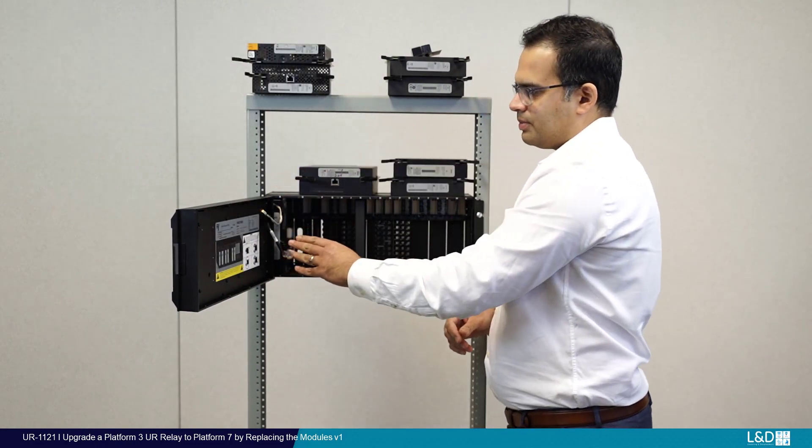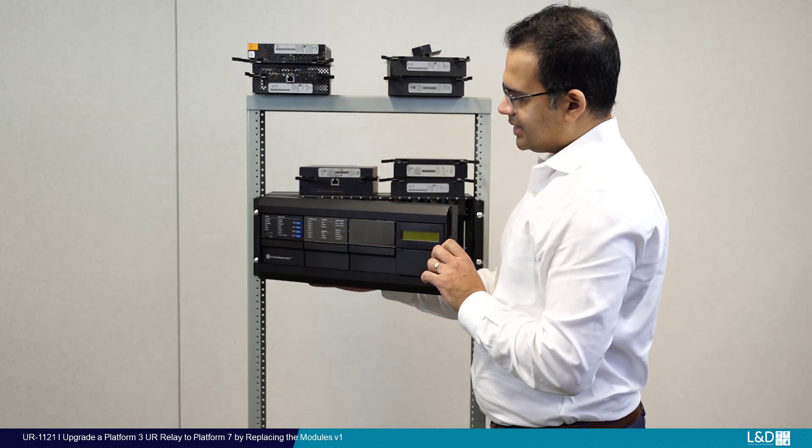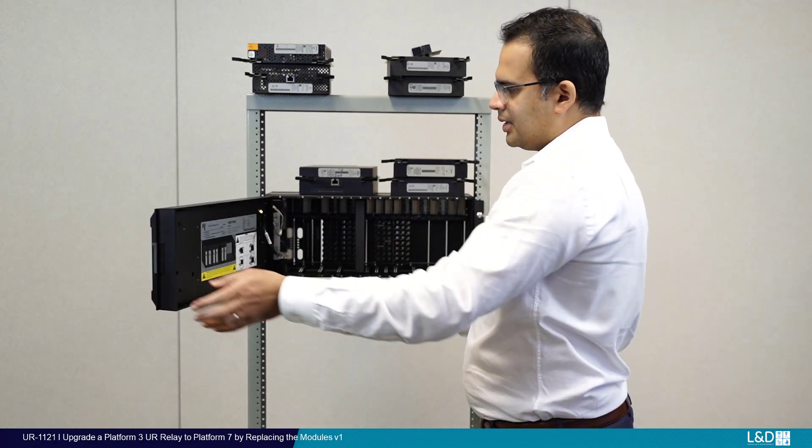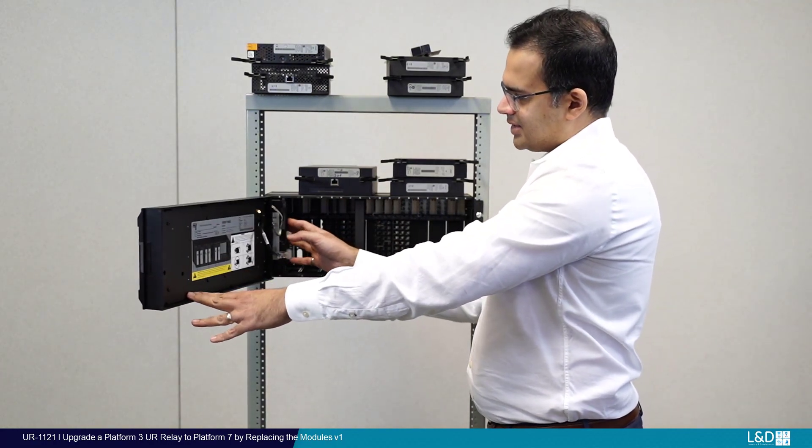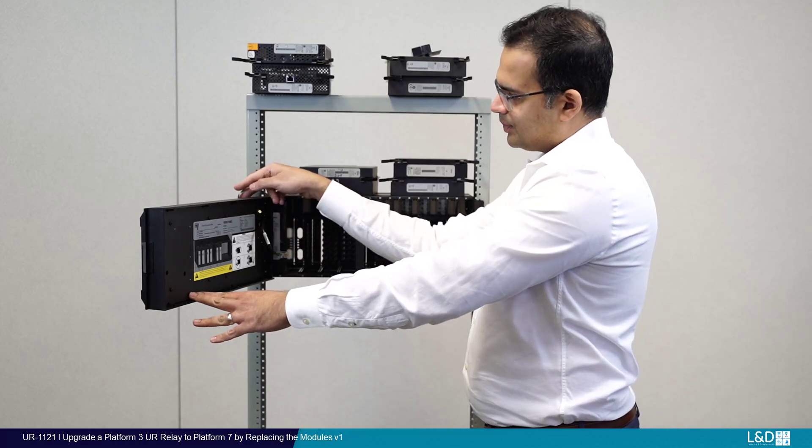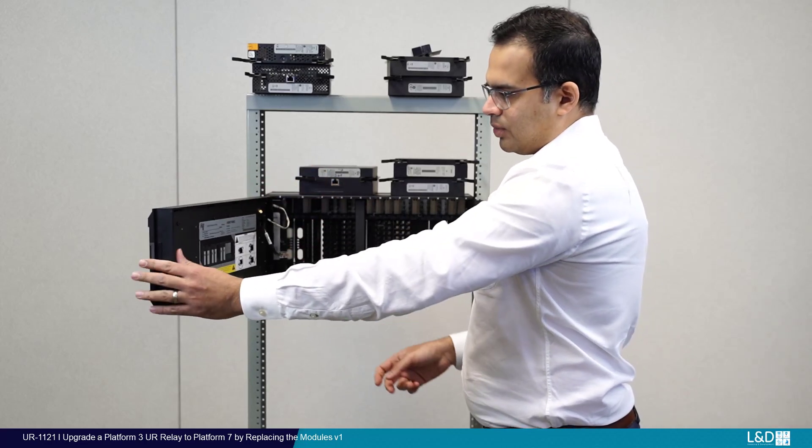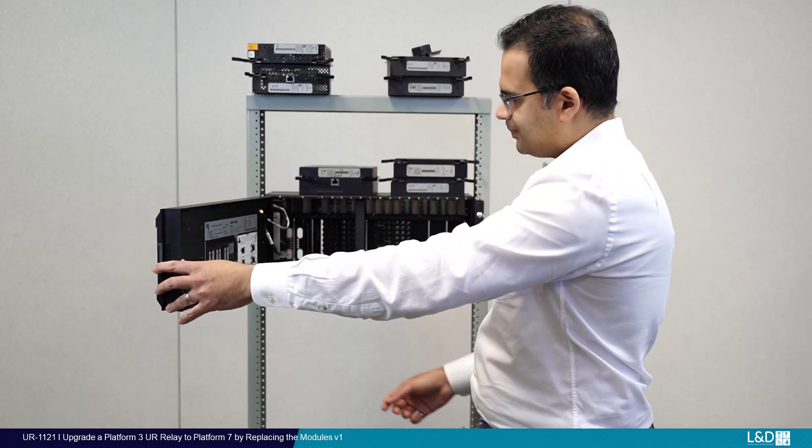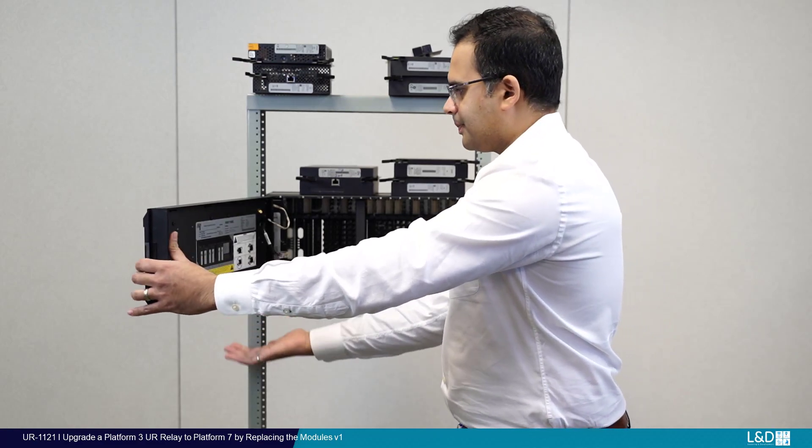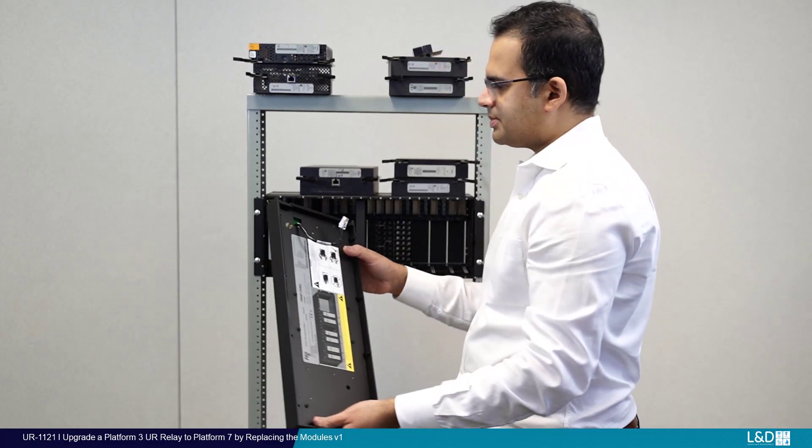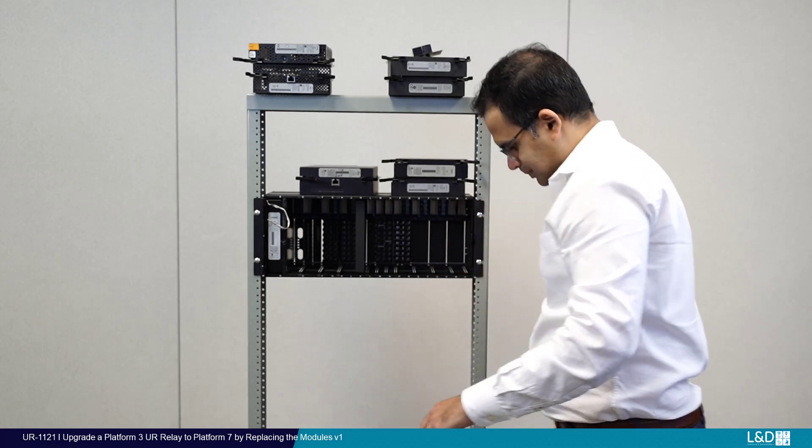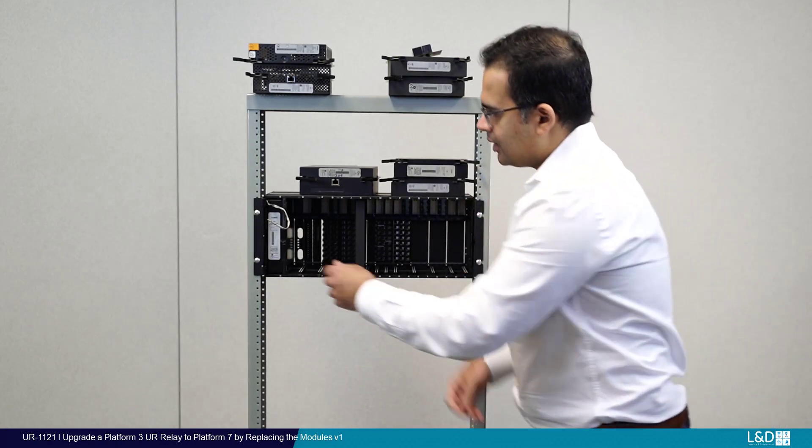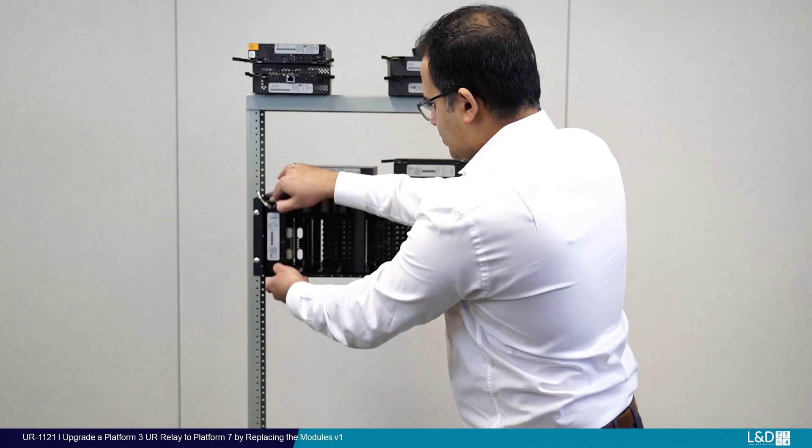If you're going to replace your power supply on this style of relay, it's a basic style relay with a basic style front panel, you're going to have to remove the front panel in order to access the power supply. The way you do that is you open the door 120 degrees and give it a slight tap from the bottom and it just pops out of the hinge. I'm going to set that aside and we're going to remove the power supply module.